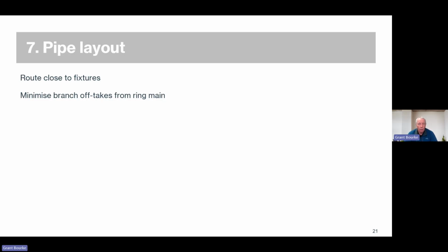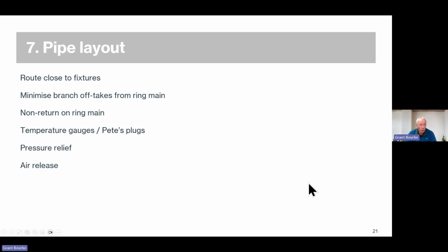Obviously, NZS 3501 copper, the T's are full bore. They still have a little flow restriction, but not huge. So just bear this in mind. Don't get too carried away if you've got lots of offtakes and you're using a PEX system that's got restricted T fittings. Non-return on the ring main we spoke about. Temperature gauges and Pete's plugs we spoke about. Some pressure relief we spoke about.